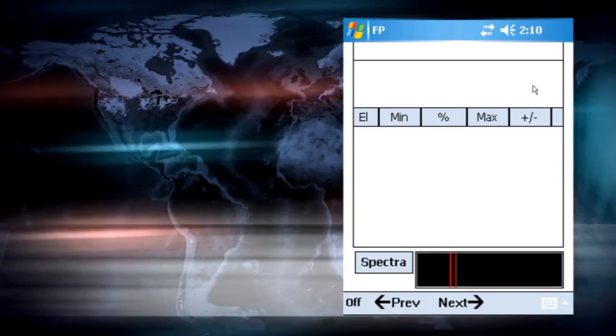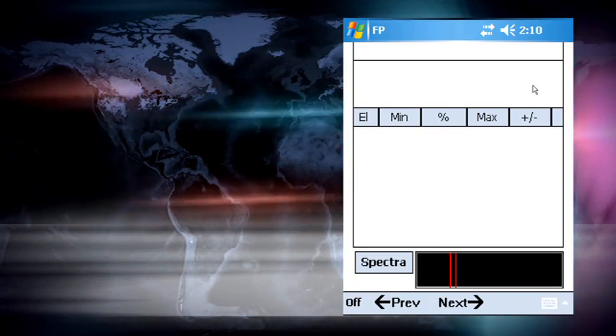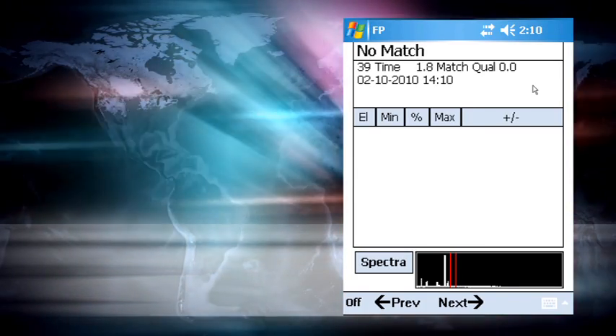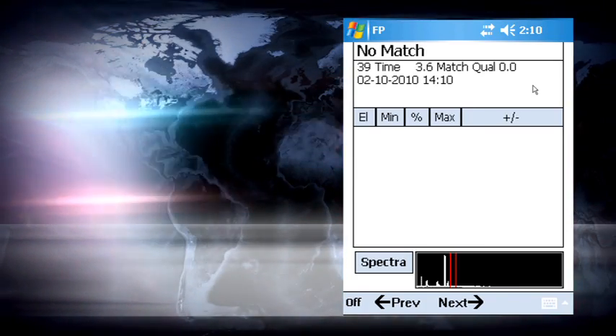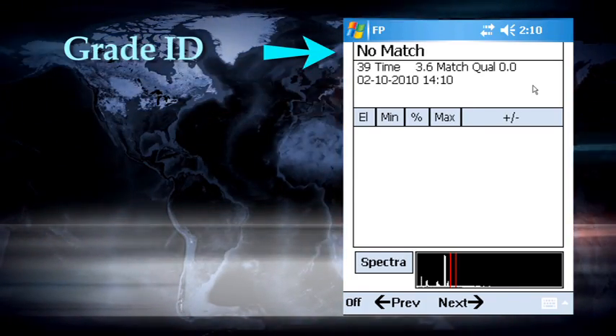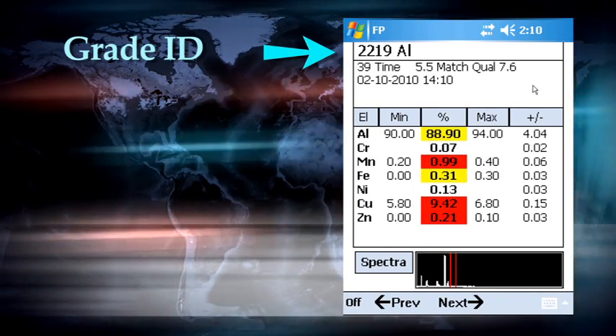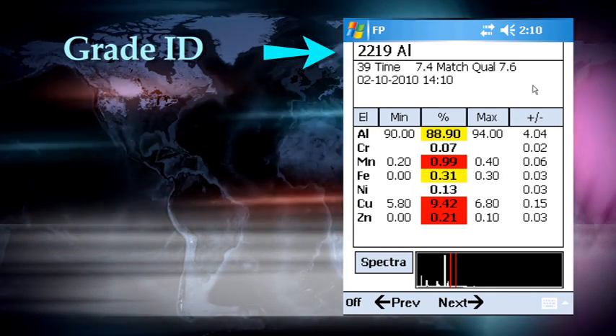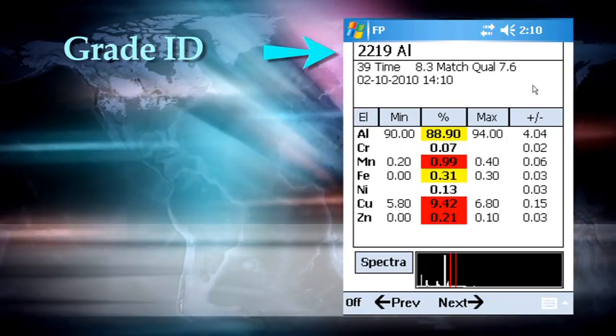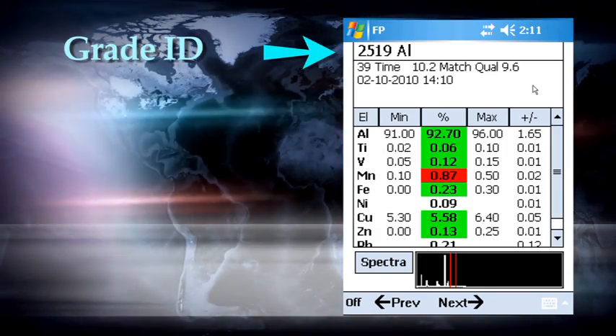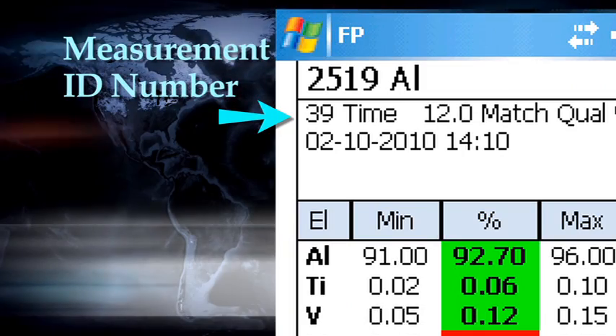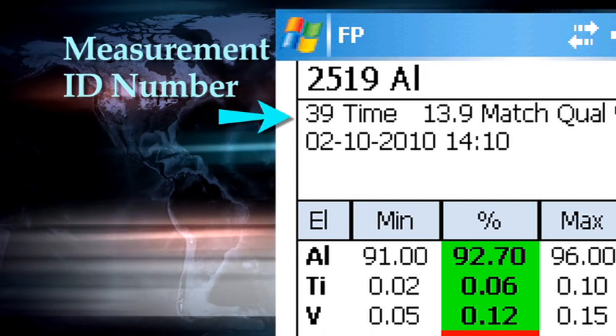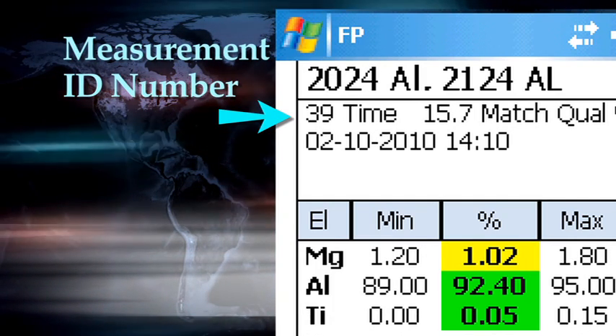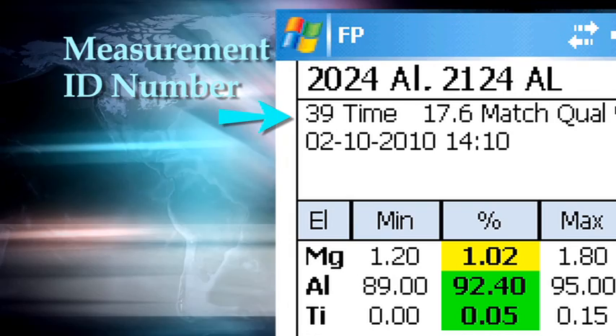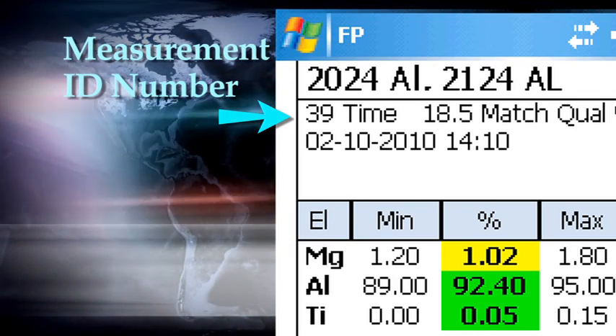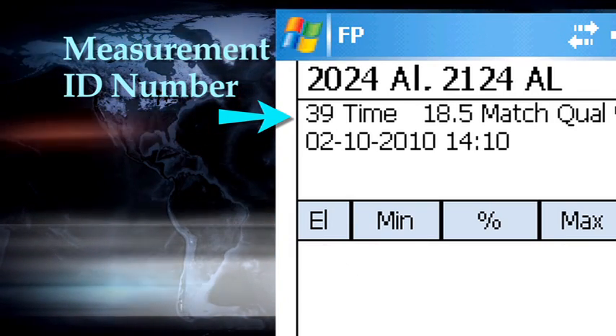When the trigger is pulled, X-rays are activated. This should quickly result in the display of a set of data on the PDA screen. This display will include the grade identification on the first line of the display. If there are several grades which are very similar, there may be up to 3 grades identified on this line. Below the grade is the measurement ID number. This number will be saved with the data and in the results file. This ID number becomes the internal identification of this sample.